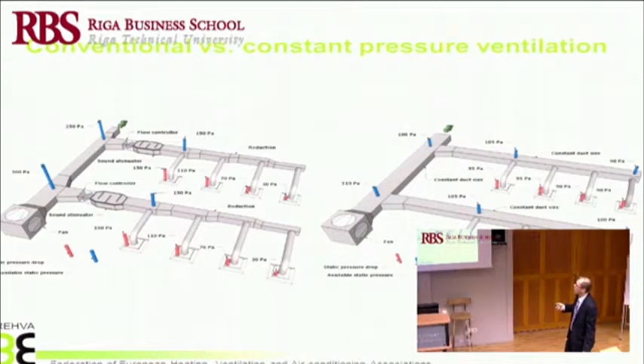So the conventional system operates with around 300 pascals pressure drop for the ductwork, but a low pressure, constant pressure one operates with around 110 pascals. So there is only a 10 pascal difference in available pressure, or 20 pascal from here to the last diffuser. And in such a case, there is no need for silencers. A large air handling unit is so quiet that sound attenuation is not needed anymore, and basically no need for dampers, no dampers here, only adjustment by the supply air terminals. And this really is very, very simple, and you can believe it's also reliable to operate such a simple system.